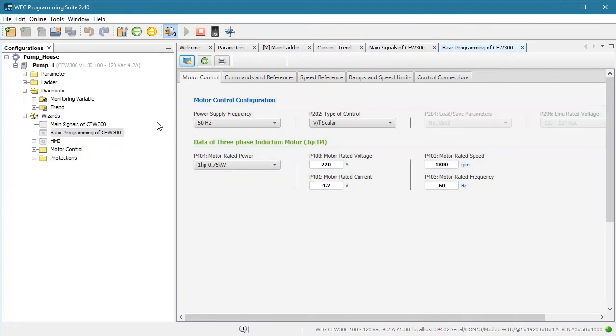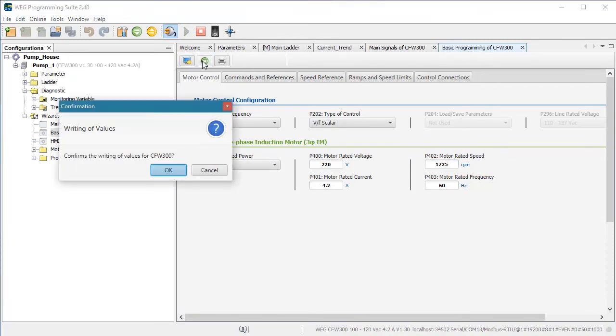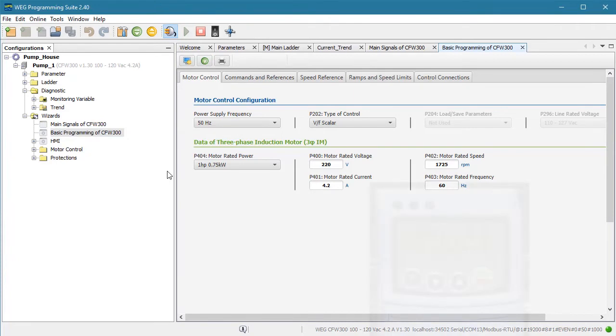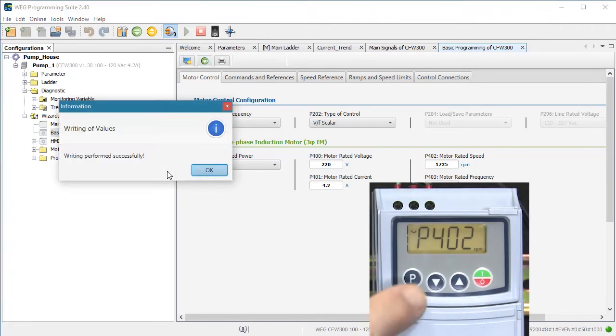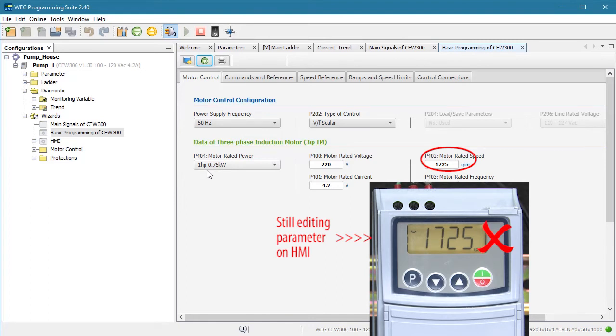Also notice that the background got a lot lighter when I deselected the monitor button. That's to remind you that you are not in monitor mode. So to write values, just change any of the offline parameters you want and hit the write button. And we see the result appear at the drive. One side note, you can't write to the drive while you are editing a parameter on the drive.